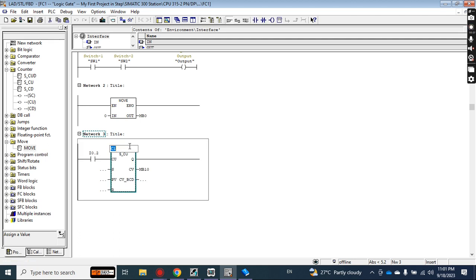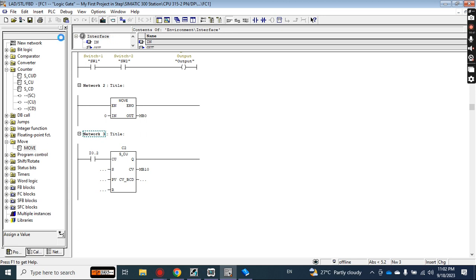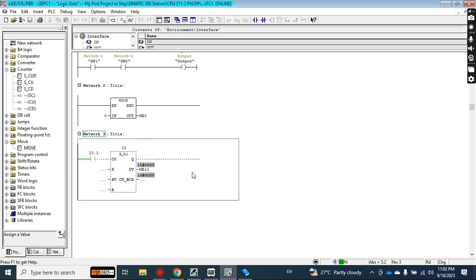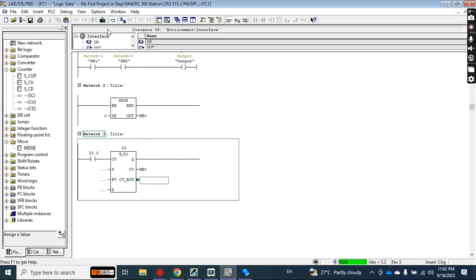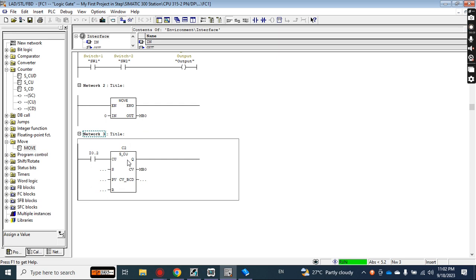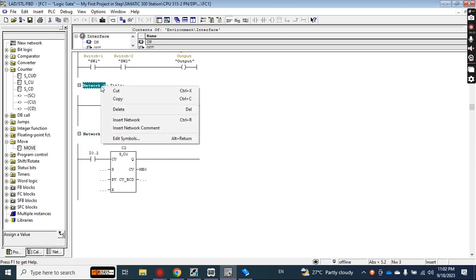I remember why this is happening — I used counter C1 before, which was already storing values in those memory locations. Let me change to counter C2 to make it clearer. When you do programming you sometimes get unexpected results. I've now assigned counter C2 with memory address MB0 and removed the previous conflicting block. Save and download.